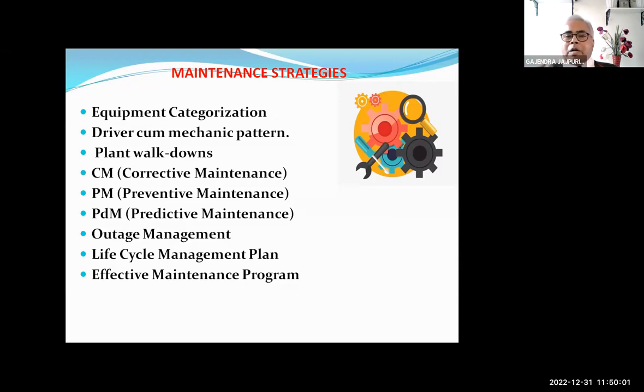Usually a transformer comes in a packed condition, so it is not visible. Something might have happened either during transportation, or some fault might have remained from the manufacturing stage itself, which caused this. So here, using the diagnostic technology of dissolved gas analysis, we could catch the fault in a timely manner and save the transformer. Otherwise, one day this very costly transformer might have failed unnoticed, if you don't adopt this type of condition monitoring or predictive maintenance strategy. So this is a small thing which I have told.